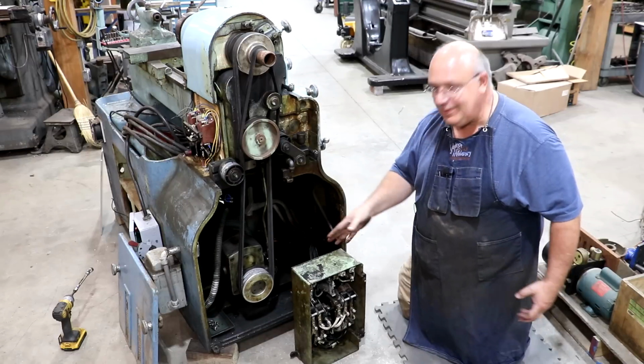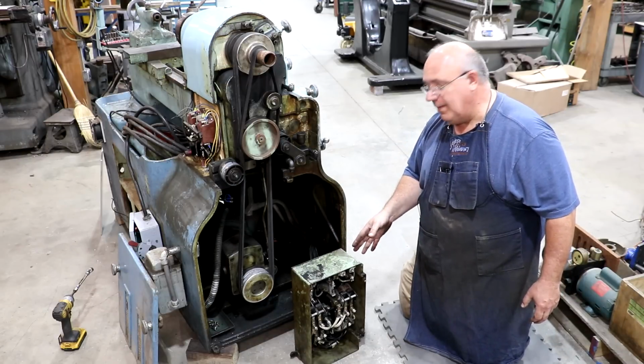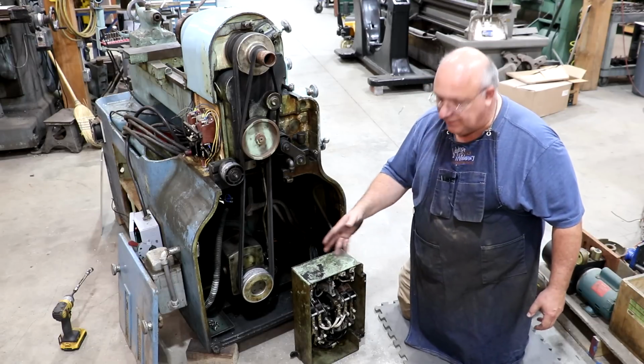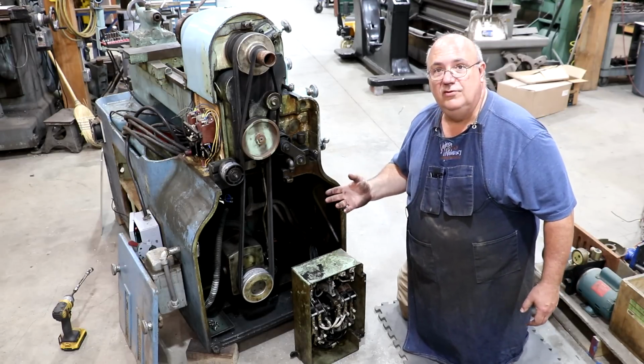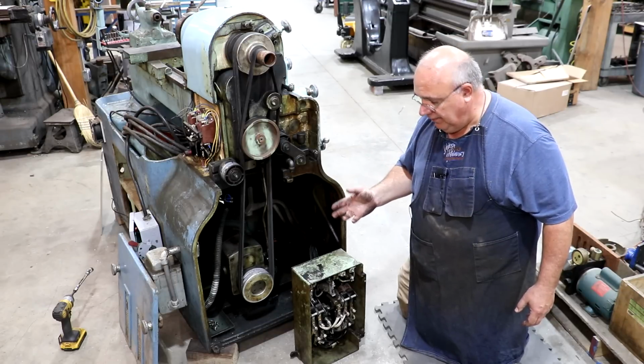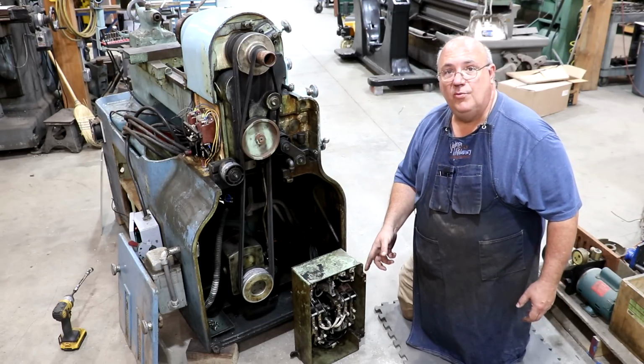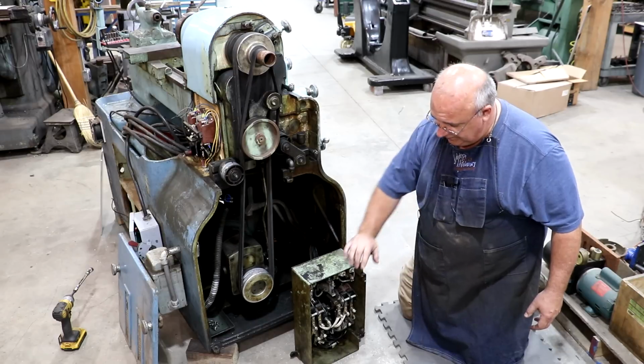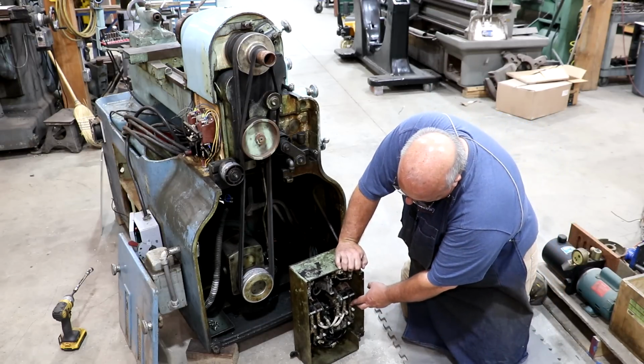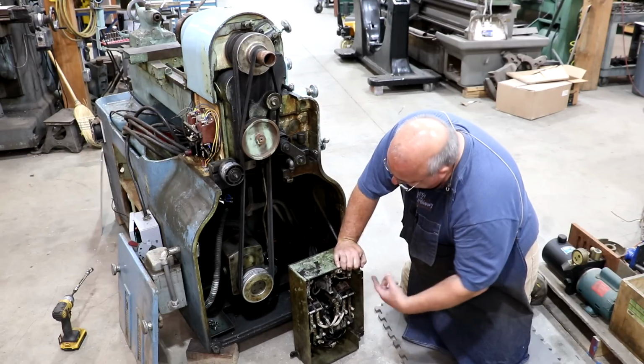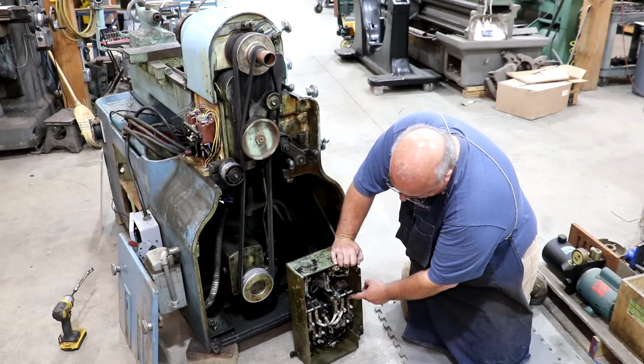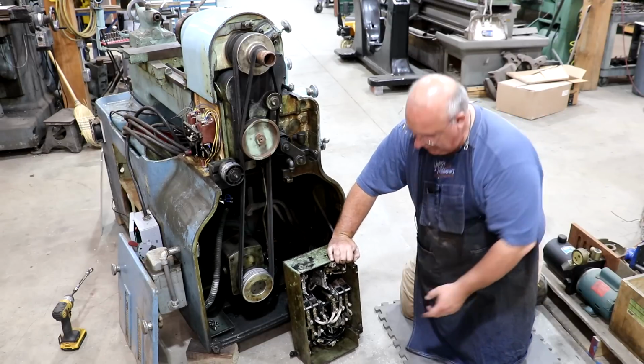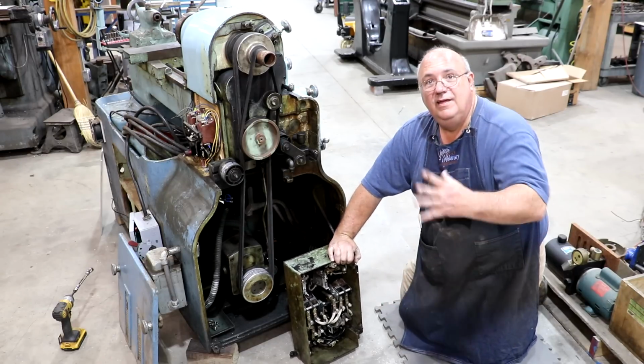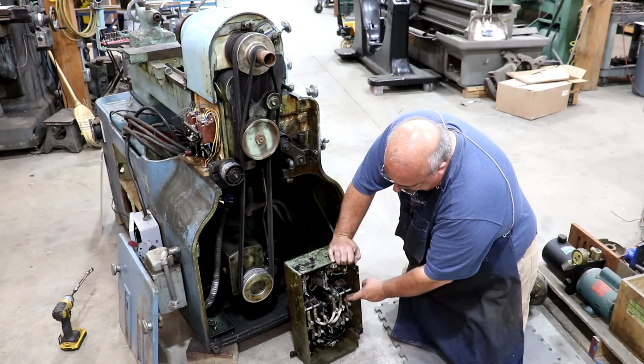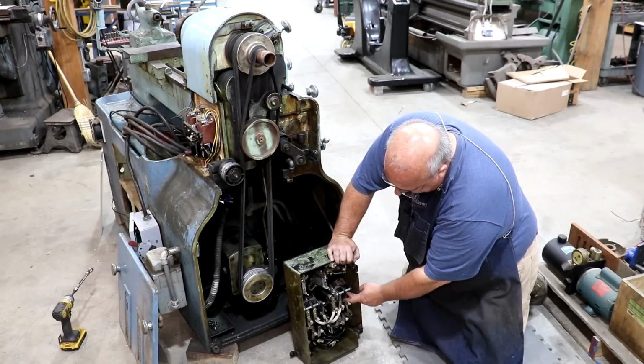In our new setup, none of this is going to be used. A lot of the functionality this box does is built into the controllers we're going to be putting on there. We are going to have some contactors, but we'll use more modern solid state contactors. When I had the old one running and took the cover off, man, you talk about a flash arc. Every time these things would engage and disengage, you'd see a spark come across them. That was pretty common with this style of contactor. But all of that's coming out, we're not going to utilize any of it.